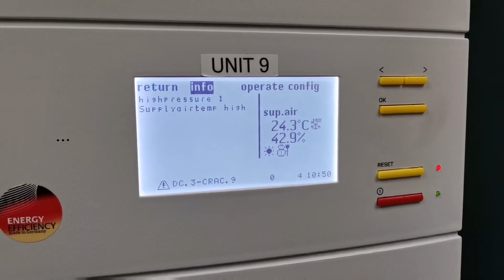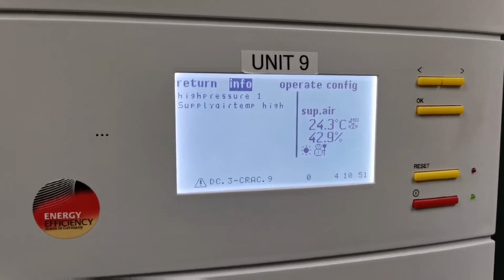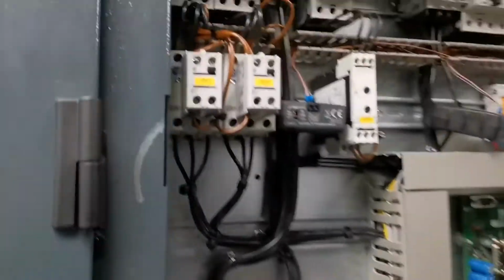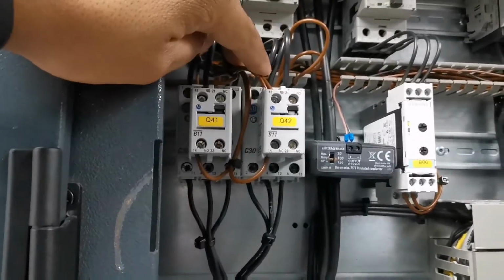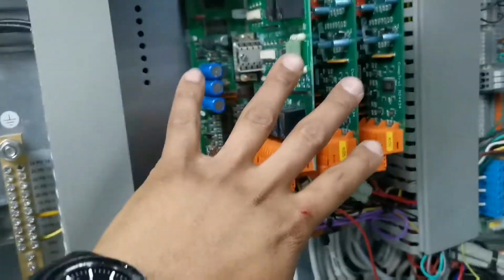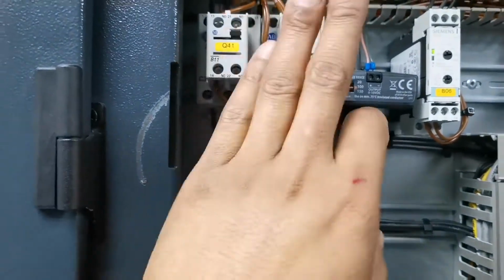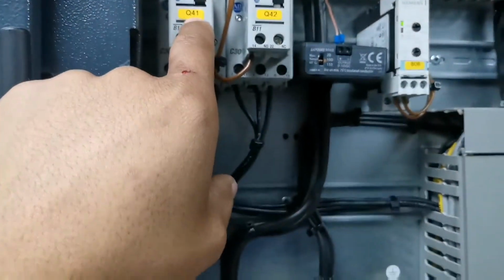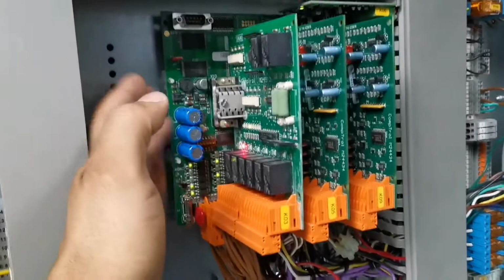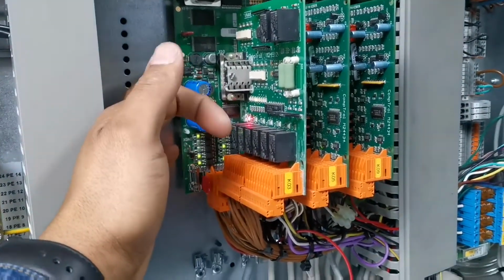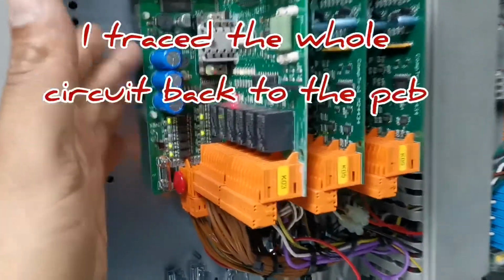Alright guys, so as you can see, we got a high pressure 1 alarm and a supply air temp high alarm. Now we swapped around the control wires on the 2 contactors. The logic board does not know which one is contactor 1 and which one is contactor 2. So the fact that we're still getting HP, even though our HP switch is not triggered, this compressor is running, this one is not triggered, tells me that we have an intermittent fault somewhere on the board. So we're gonna call tech support again and find out what their recommendations are, but I think that's gonna be our problem, guys. So thank you.